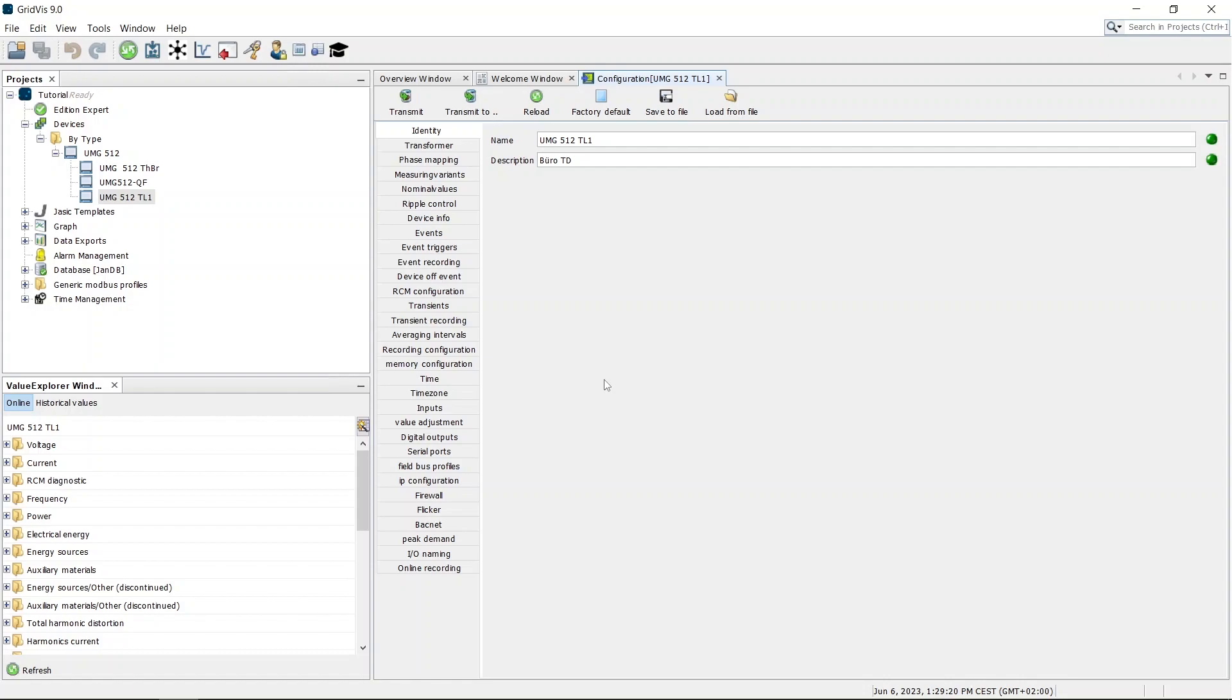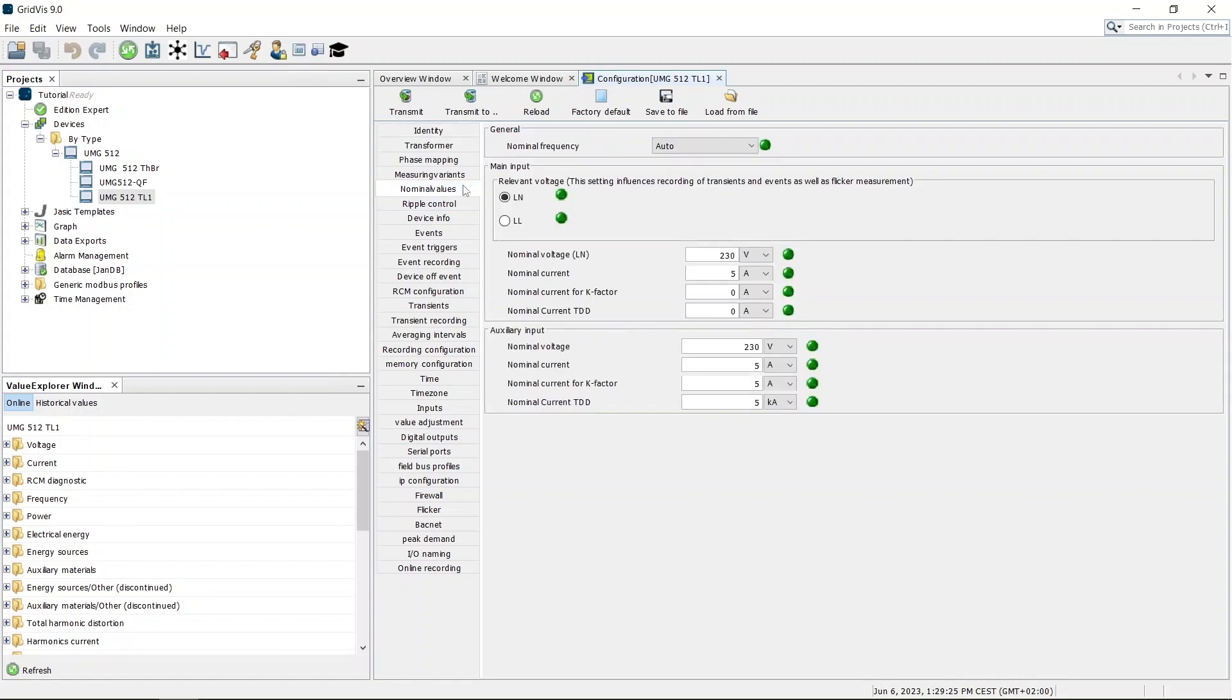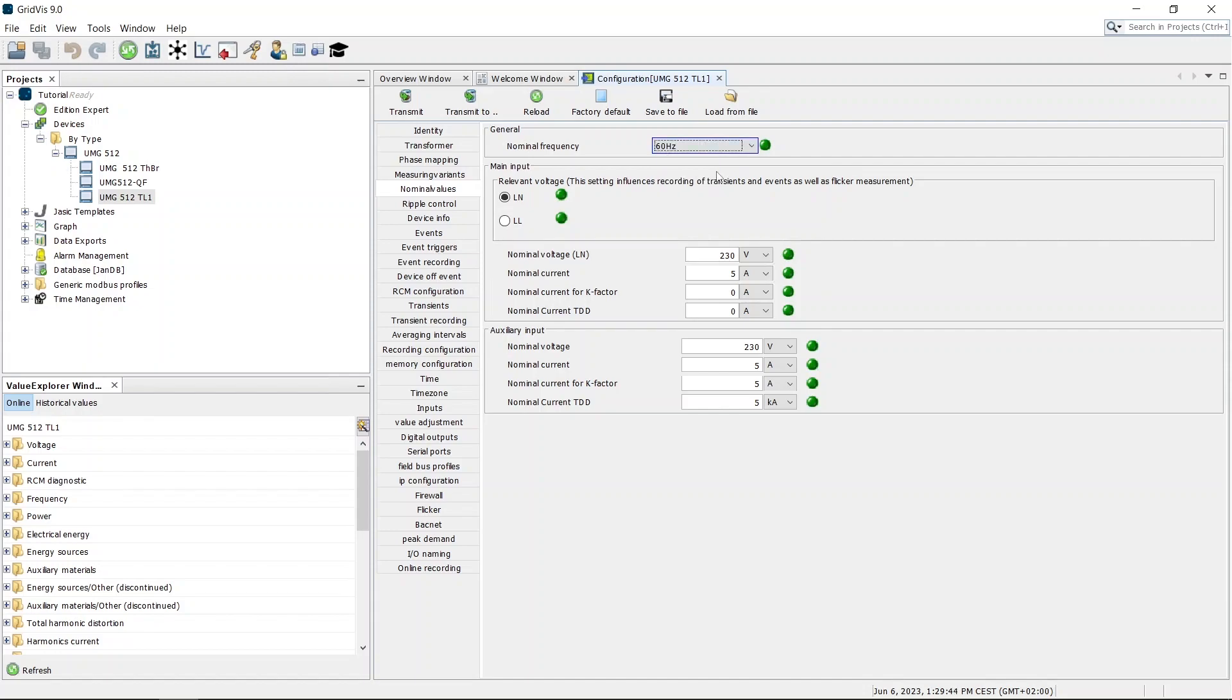Open the configuration of the nominal values. The nominal values are the basic performance characteristics of the system you are measuring. Set the nominal frequency. Either assign a fixed value or have the nominal frequency determined automatically. Specify whether the voltage is to be measured between phase and neutral or between phase and phase.